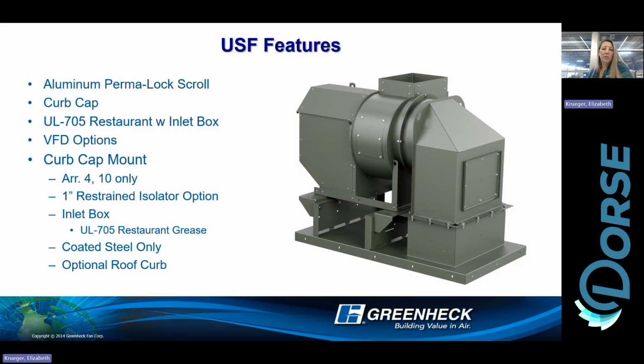Isolators, again, just basic background on those. We're going to put restrained type isolators so that if the fan is outdoors, again, all USFs are made to go outdoors. Even though 50% of the applications that I've seen are indoors, they are meant to go outdoors. If they do get put outdoors, we want to restrain those isolators. Otherwise, the wind loads can tip those fans off. So be sure to choose restrained type if you are putting the fan outdoors.